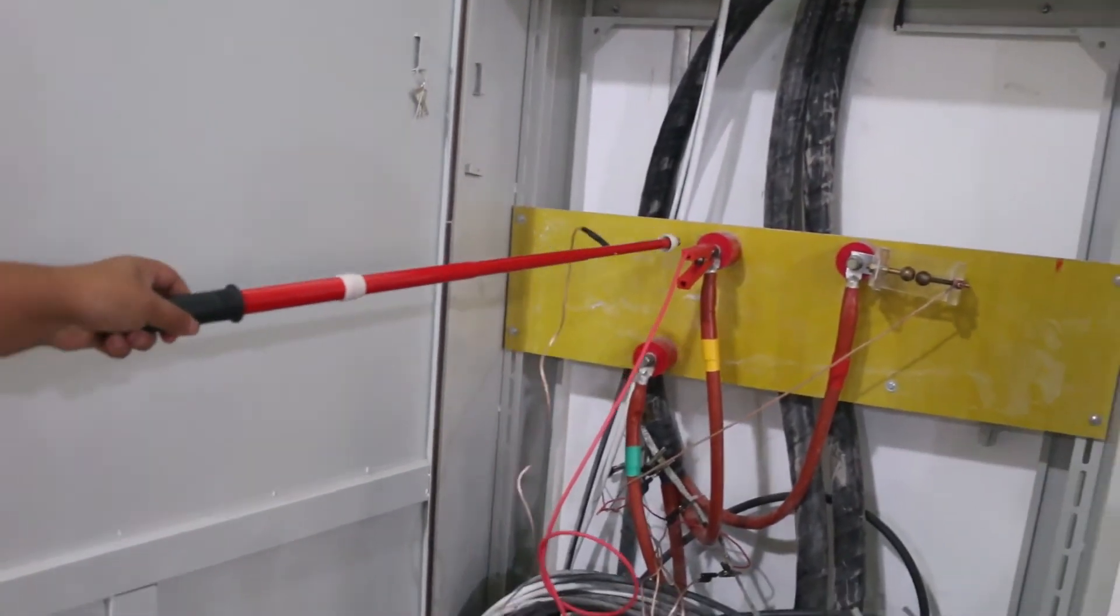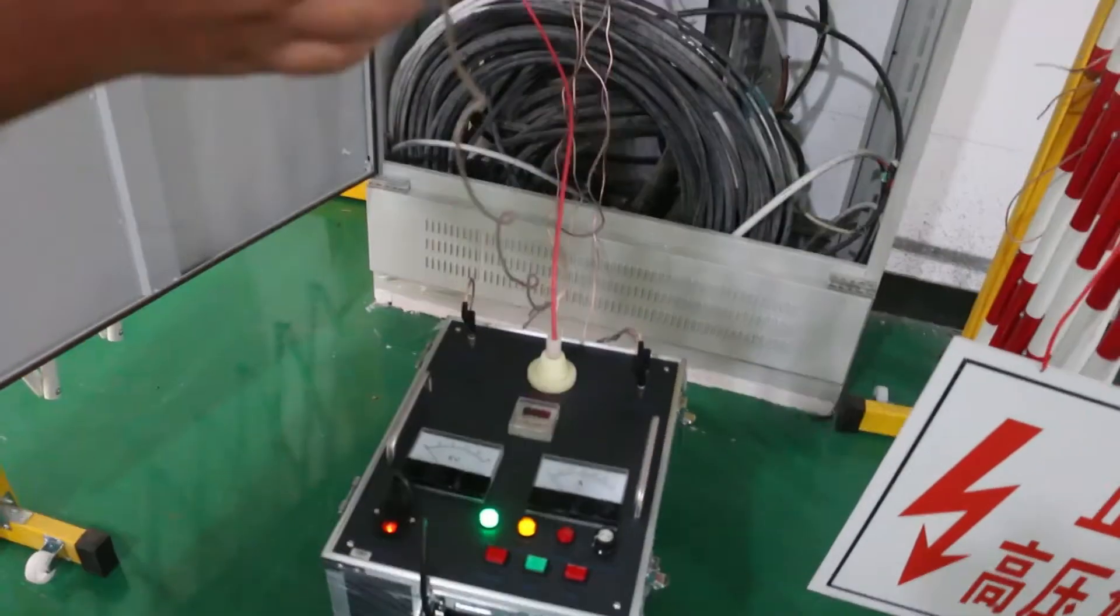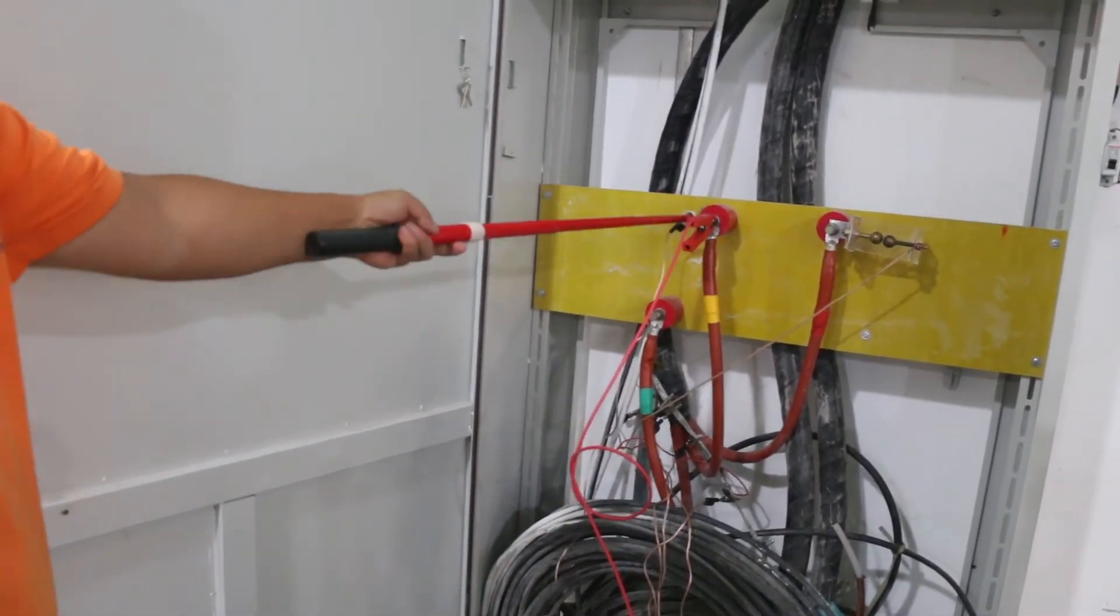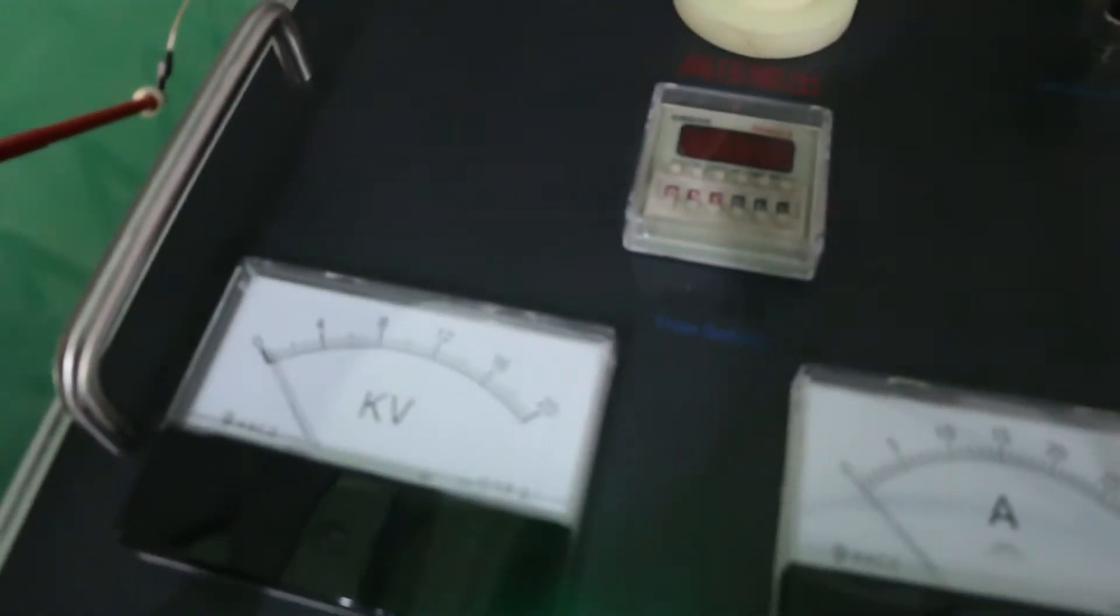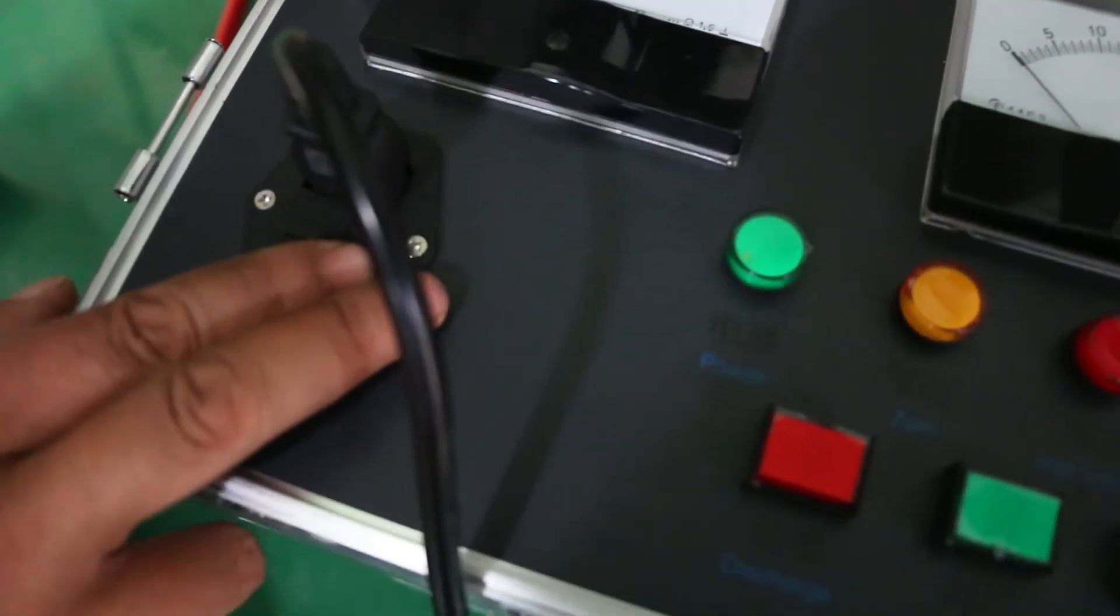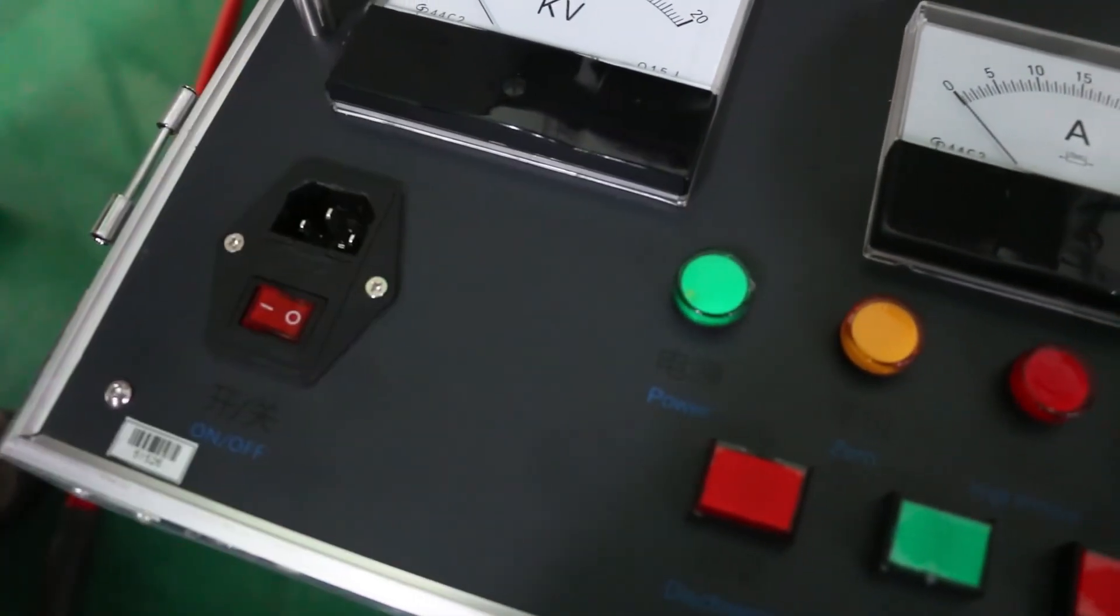Then use a discharging rod to touch the core of cable and press discharging button to discharge. When the voltmeter goes to zero, the discharging is complete. Turn off the machine, disconnect plug, and collect leads.